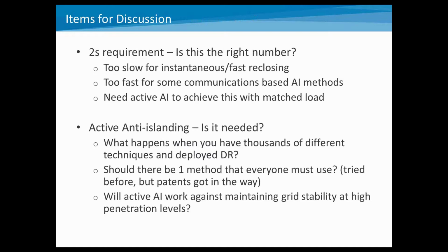So a couple items for the discussion. I just wanted to throw these out, and I'm sure we'll have some discussion here in a second, but some comments on this. Obviously, there's a 2-second requirement in 1547 right now, and the question is, is this the right number? Some things to think about. It's too slow for instantaneous reclosing. So if we have on the distribution system utilities using instantaneous or super fast reclosing circuitry, that happens within 2 seconds. And so it's not going to be coordinated with that anyway.